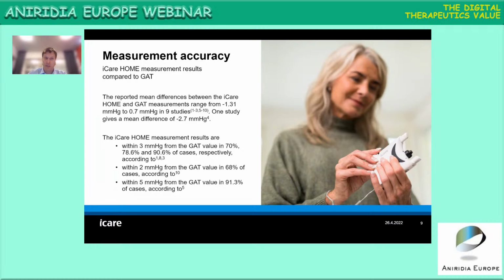The measurement accuracy: iCare Home measurement results compared to Goldmann applanation tonometer. The reported mean difference between iCare Home and Goldmann applanation measurements ranges from minus 1.31 millimeters of mercury to 0.7 in 9 studies. One study gave a mean difference of minus 2.7 millimeters. So the difference with Goldmann applanation is very small. The iCare Home measurement results are within 3 millimeters of the Goldmann value in 70%, 78 and 90% of the cases respectively according to the studies. Within 2 millimeters of the Goldmann applanation value, 68% of the cases, and within 5 millimeters of the GAT values in 91% according to the studies, which I'm referring to here. At the end of the presentation, there's a list of the studies.